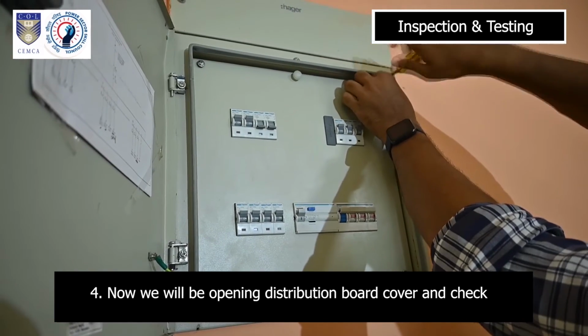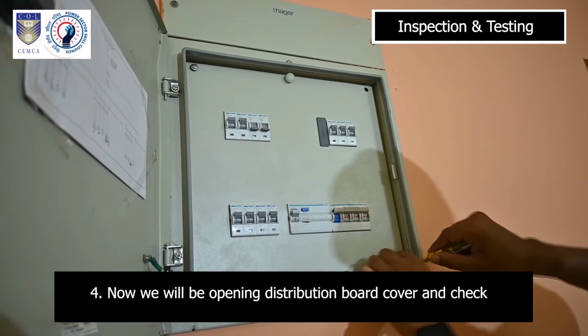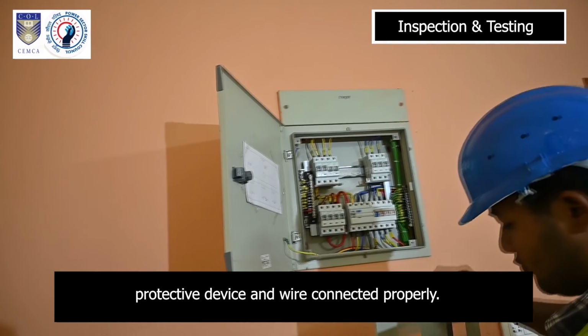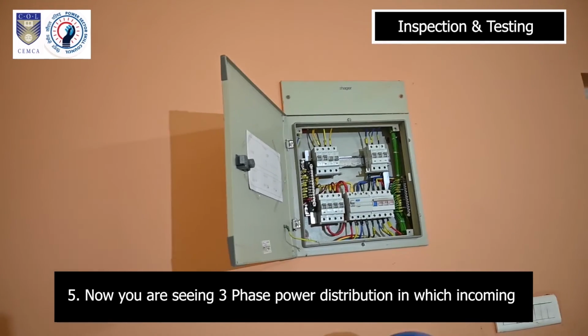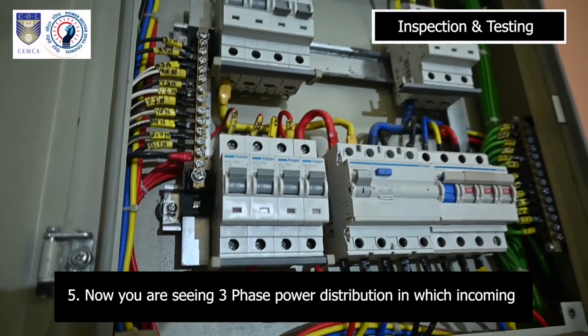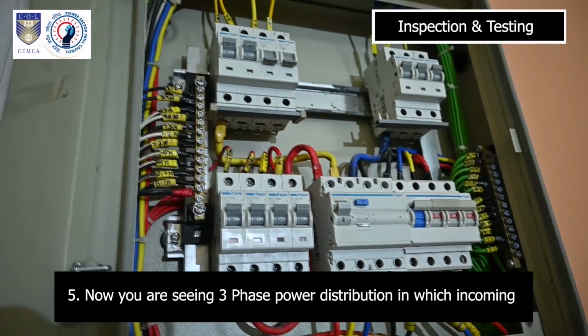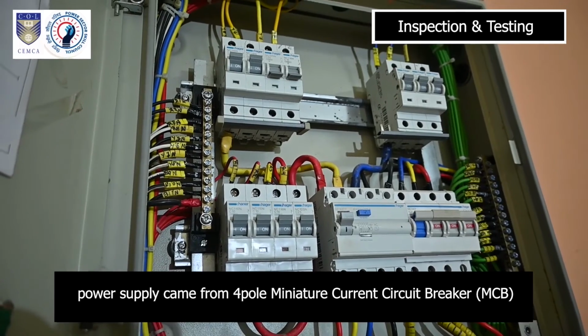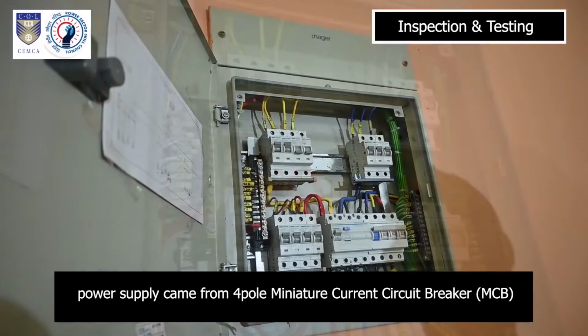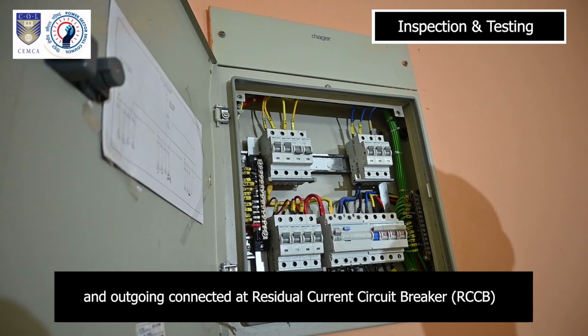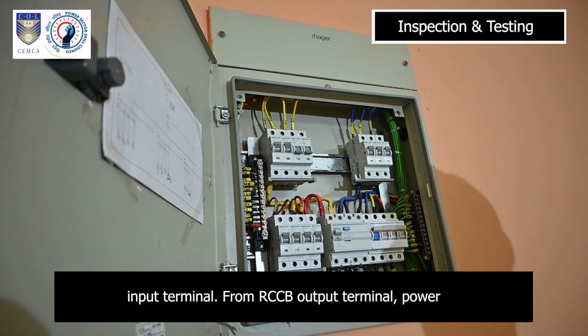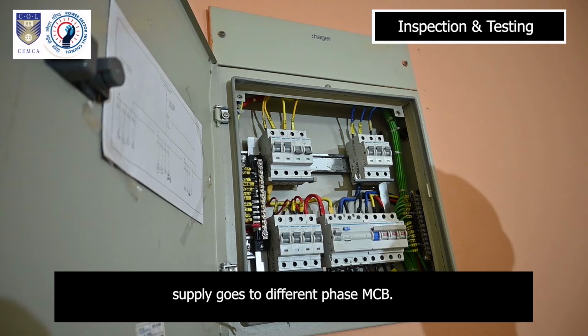4. Now we will open the distribution board cover and check that the protective device and wires are connected properly. 5. Now you are seeing 3-phase power distribution in which the incoming power supply comes from a 4-pole miniature circuit breaker (MCB) and the outgoing is connected at the residual current circuit breaker (RCCB) input terminal. From the RCCB output terminal, power supply goes to the different phase MCBs.